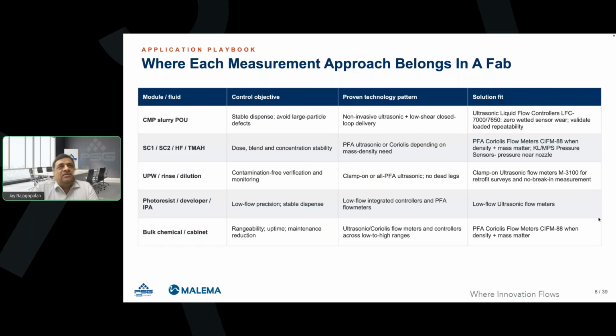For CMP slurry, the stable dispense is critical, not only the flow rate but also the flow volume. How stable it is while the flow rate is maintained for the dispense cycle. So non-invasive ultrasonic type of flow technology is usually preferred. In case of Malema, the ultrasonic flow controller 7000 is often used in those applications. For aggressive chemistries like SC1, SC2, and hydrofluoric acids, the objective is often how it is dosed, blended, and maintaining the concentration. In this case, both ultrasonic type of product as well as Coriolis mass flow based technologies are used.